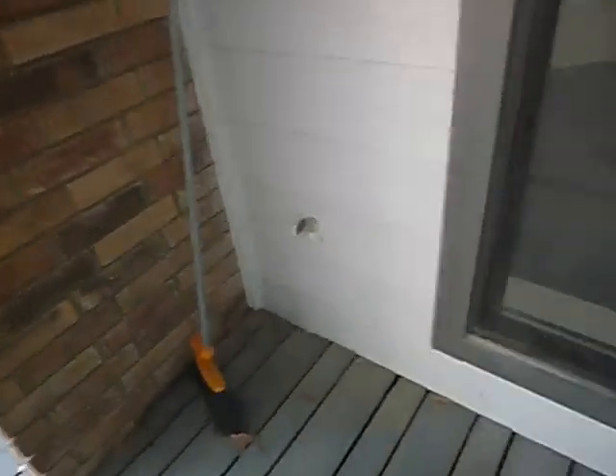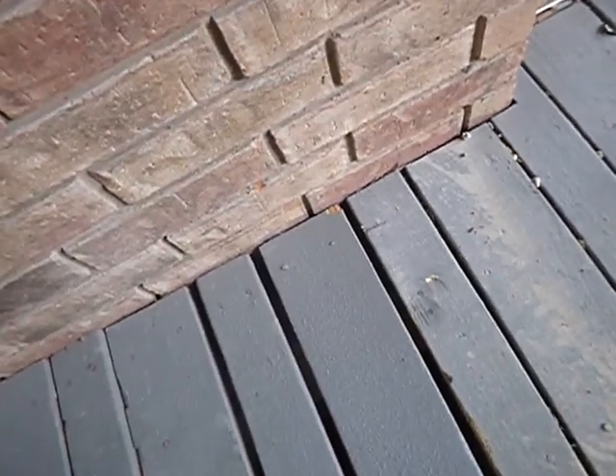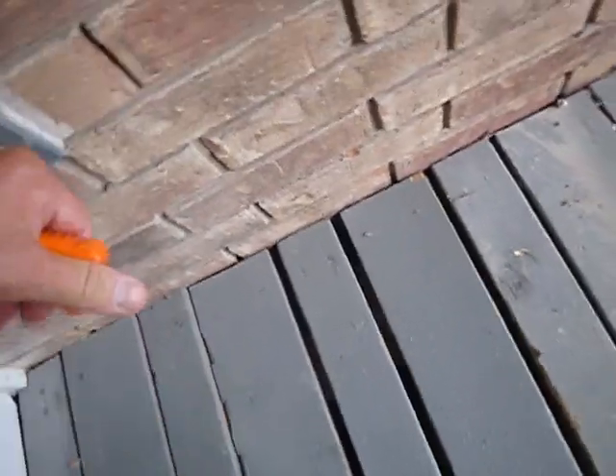This one — because we are underneath the patio, it's a judgment call. My judgment is that these receptacles should not have to have in-use covers because they're already protected pretty well by the overhead patio. The report will be a little more vague and say 'some,' and you can use your own judgment.